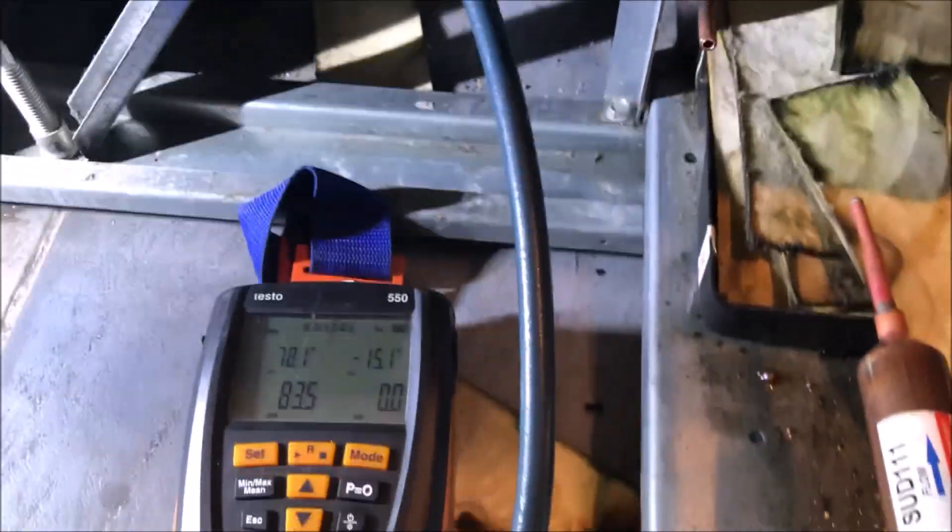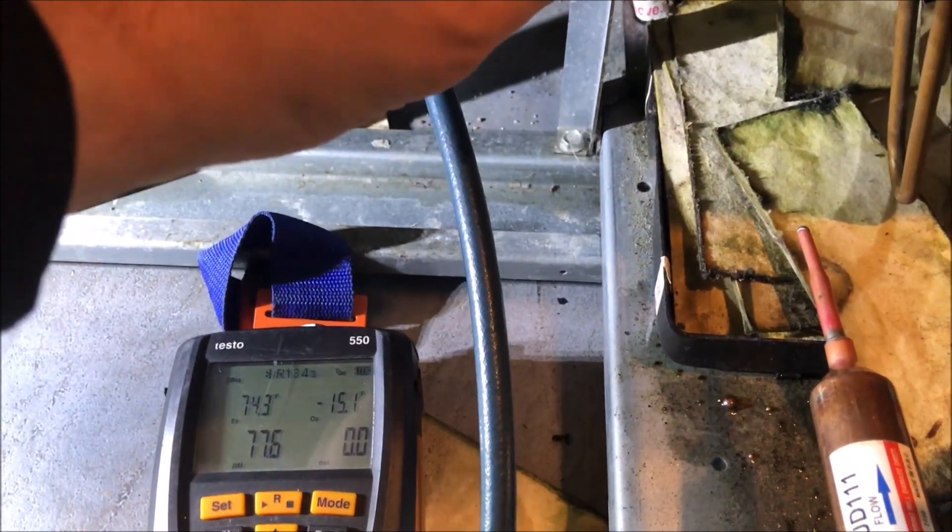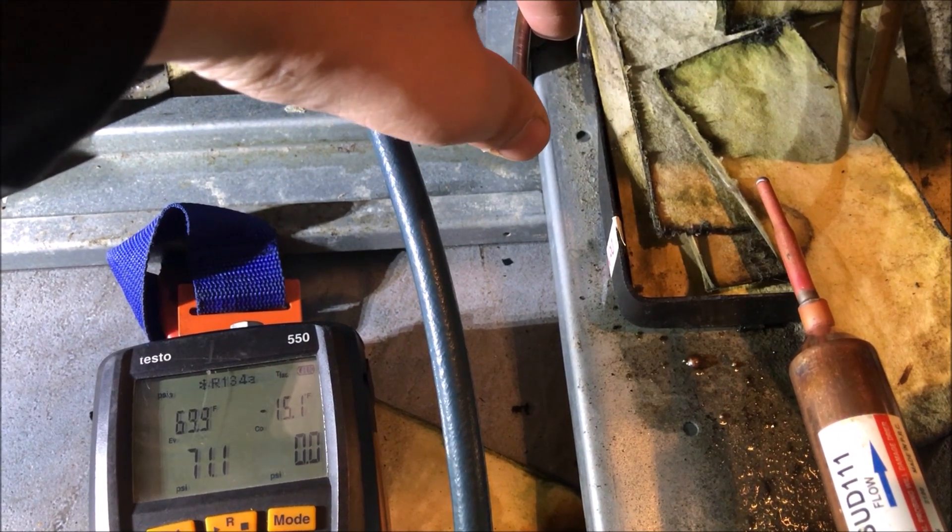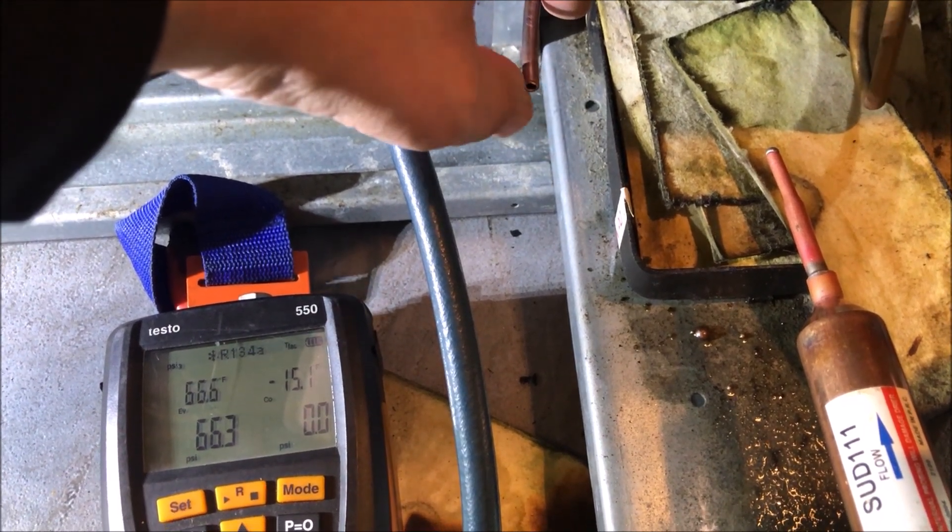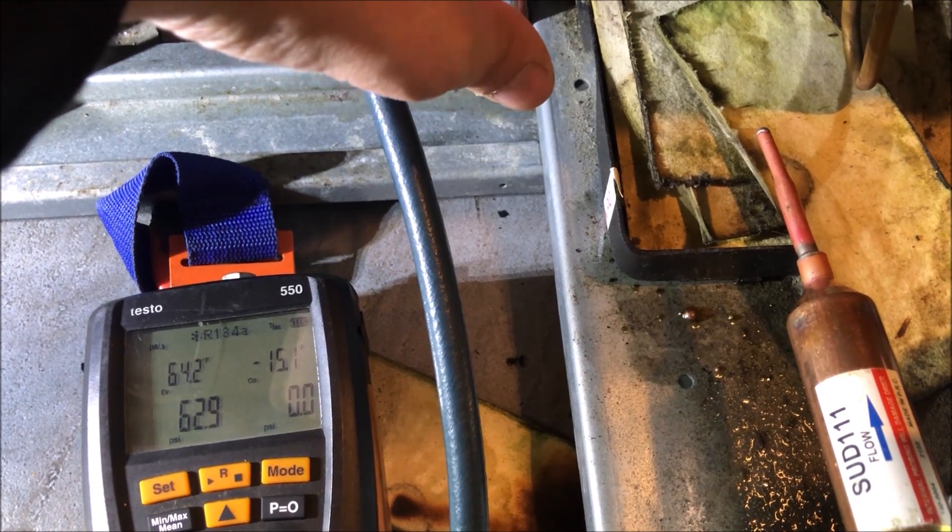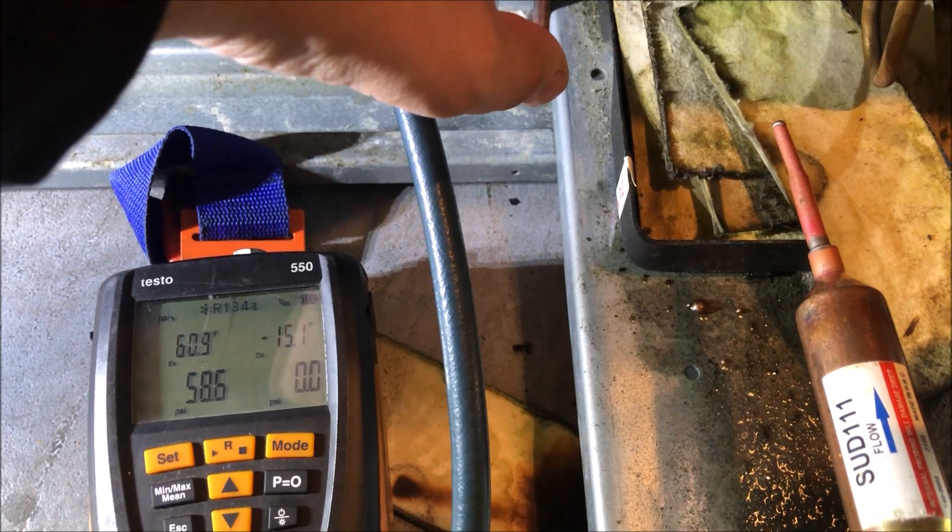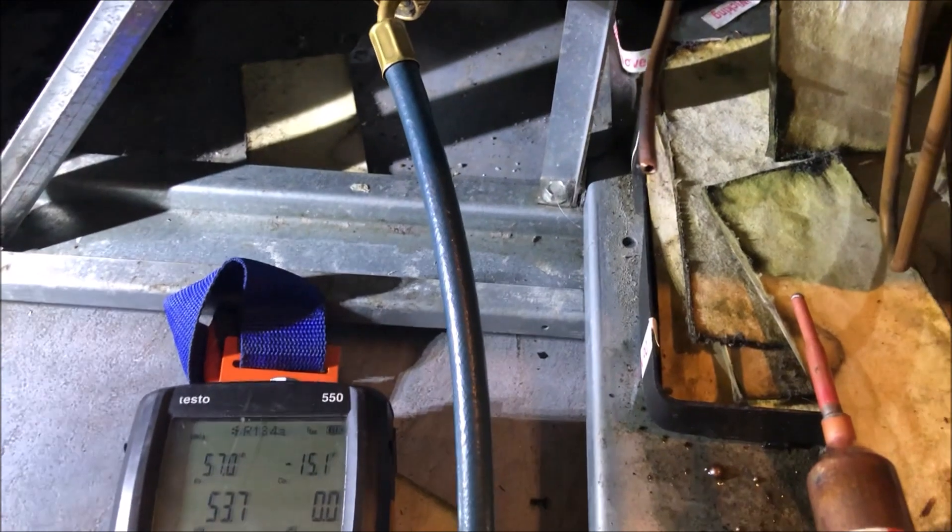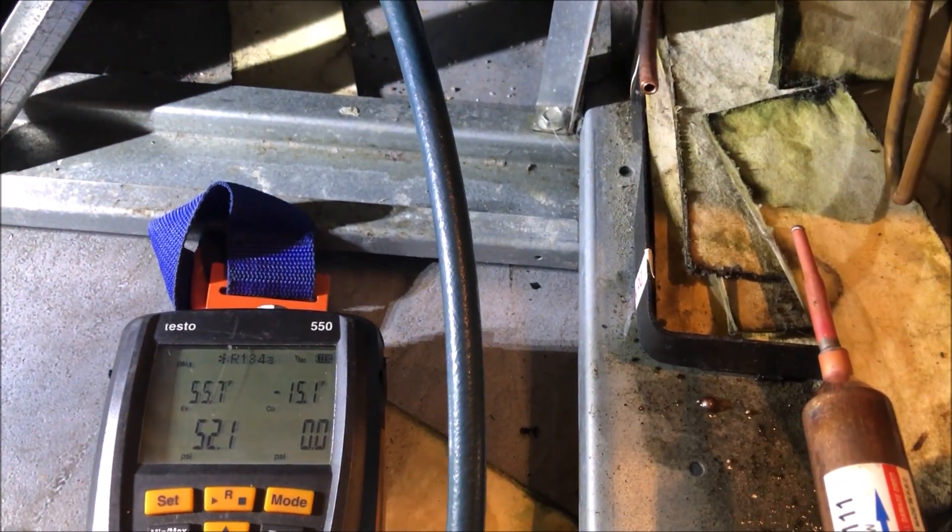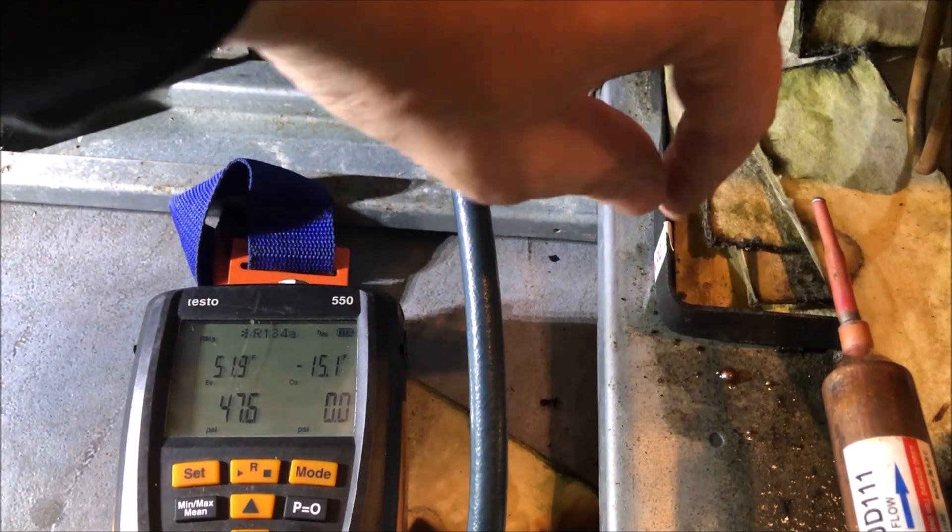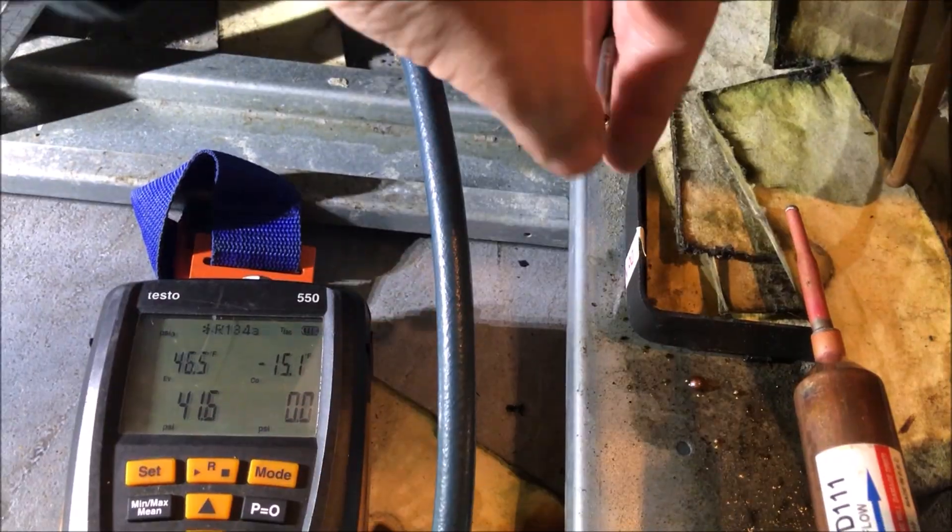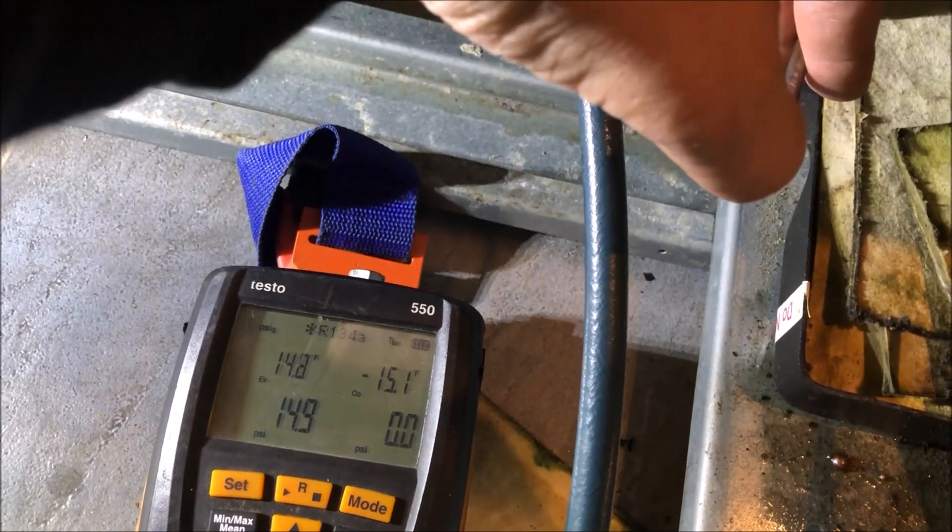I've had good flow at 70, 80, 60 PSI, but when I get down to 14 or even 10, the flow's almost minimal. That means you still have a restriction, so it's very important that we keep testing as we're going along. You can see I'm putting my thumb over it to just kind of surge the nitrogen through. And then right when we get down to our operating pressures, which will be somewhere around that 12, 13, 14 range, that's when I want to make sure that we have good flow. We'll just fast forward this part really quickly and let's get down to where we want to be.